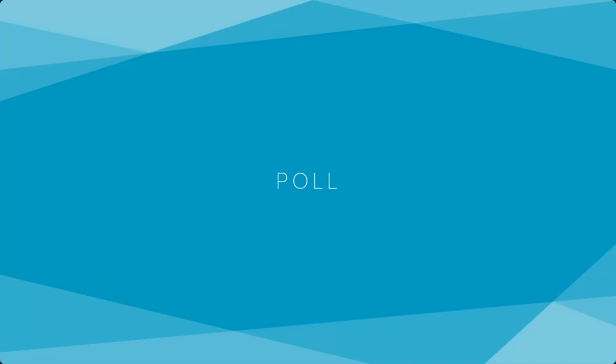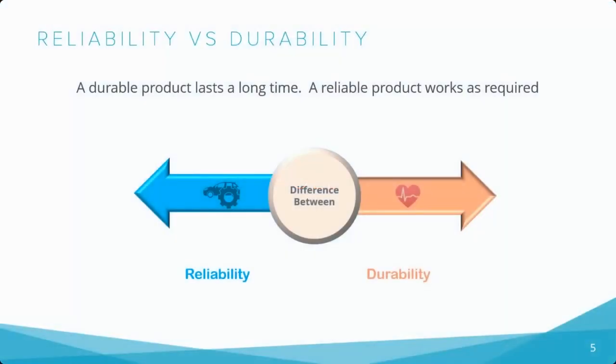Let me explain. IEC standards for safety of electromedical devices, the IEC 60601 family, define requirements to achieve basic safety and essential performance. IEC 60601 third edition addresses reliability by stating that reliability of functioning is regarded as a safety issue, and where interruption of an examination or treatment is considered a hazard for the patient. And even the FDA recommends a particular percentage reliability and percentage confidence for life-threatening devices. For example, emergency use injectors should have a reliability of 99.999% with a 95% level of confidence. The answer is yes.